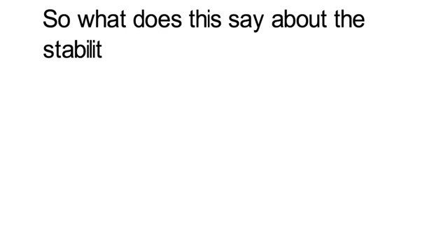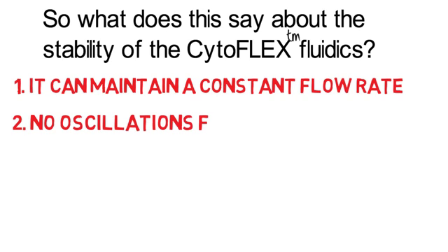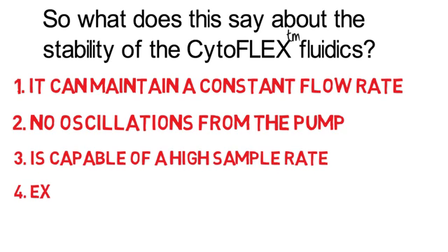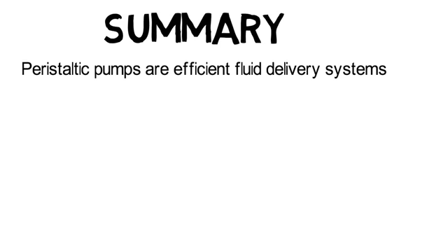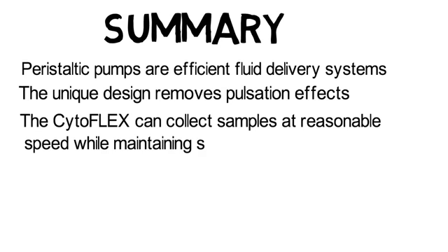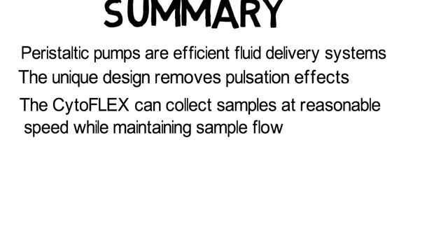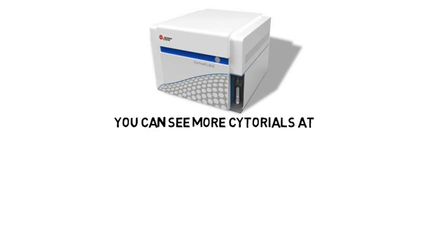So what does this say about the stability of the Cytoflex fluidics? It can maintain a constant flow rate, with no oscillations from the pump. It is capable of attaining a high stable flow rate and maintains excellent hydrodynamic focusing. In summary, the peristaltic pump is an efficient fluid delivery system. The unique design of the Cytoflex pump removes pulsation effects, and the Cytoflex can collect perfectly stable data at a reasonable speed while maintaining stable flow.